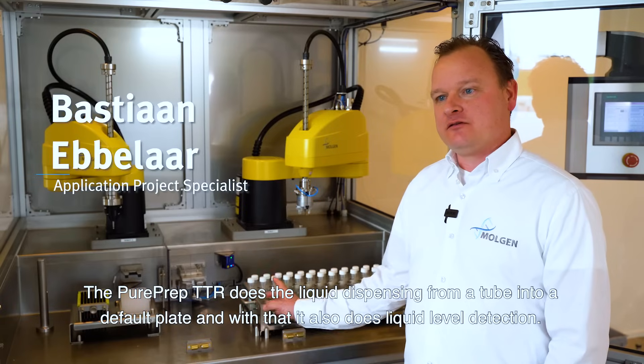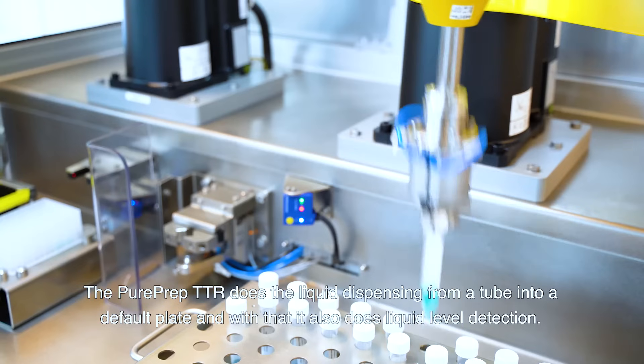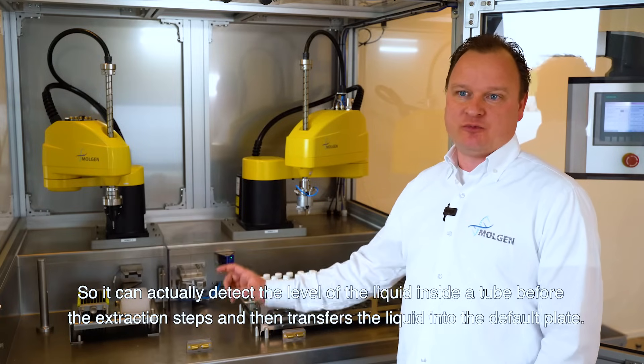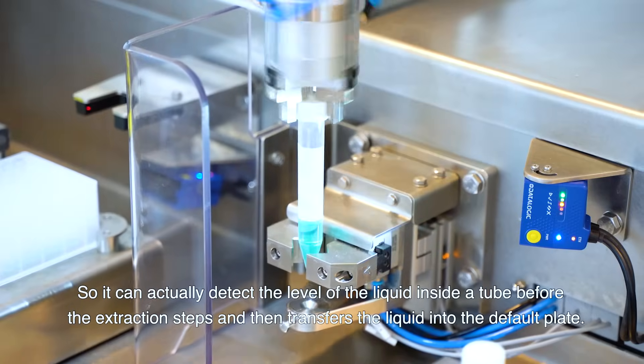The PurePrep TTR does the liquid dispensing from a tube into a depot plate, and with that it also does liquid level detection. It can actually detect the level of the liquid inside the tube before it does the aspiration steps, and then moves it — transfers the liquid into the depot plate.